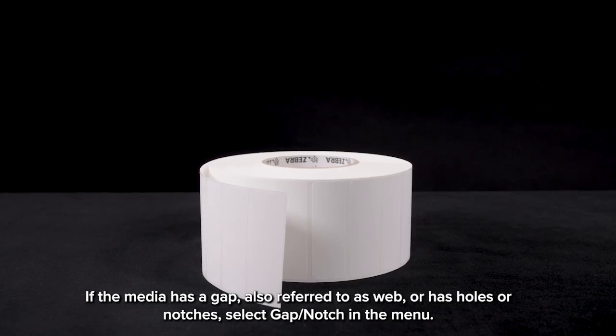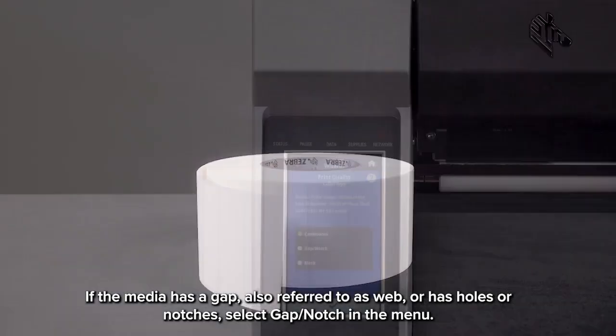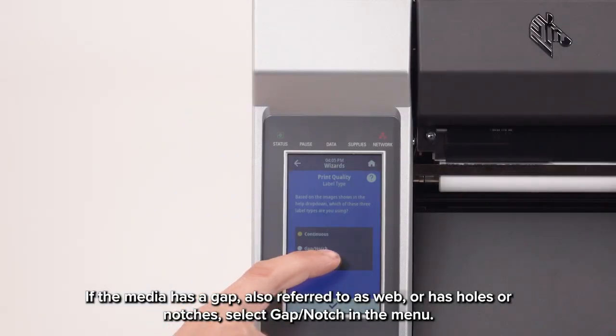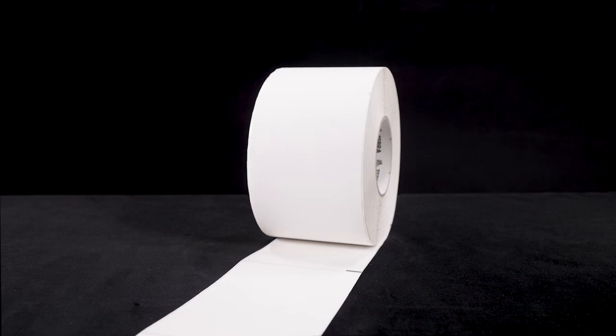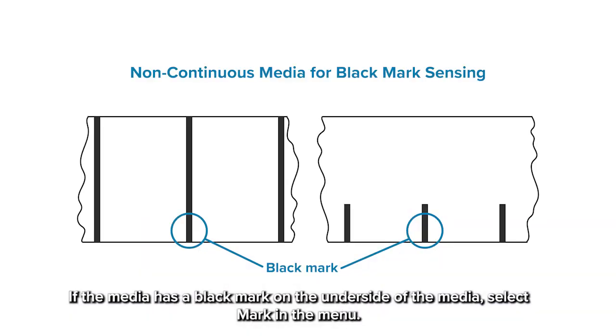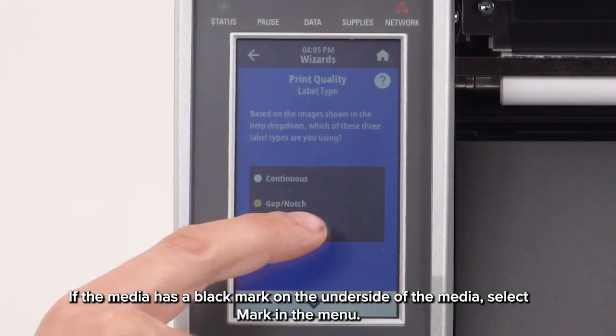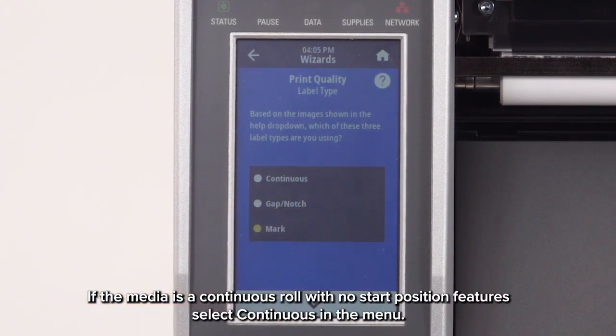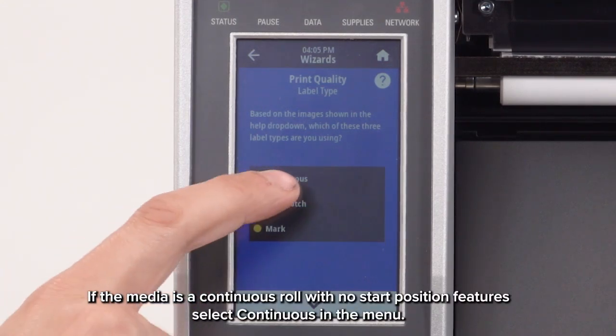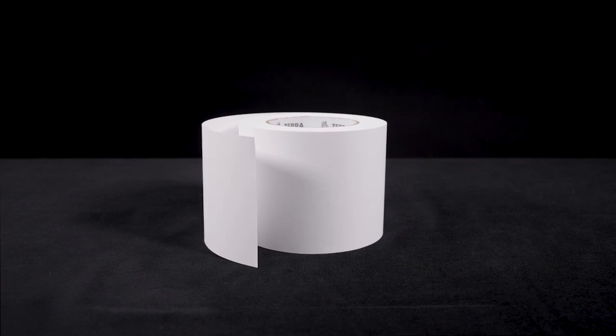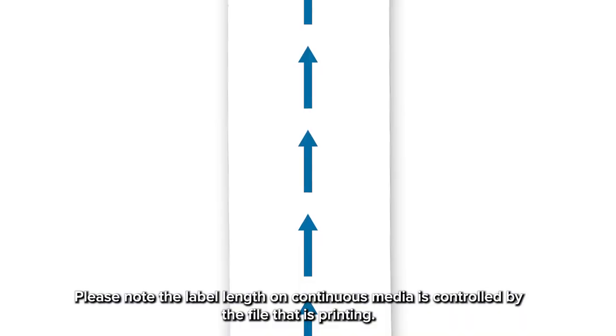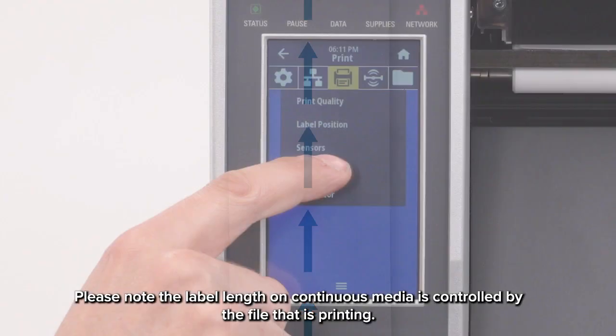If the media has a gap, also referred to as web, or has holes or notches, select gap/notch in the menu. If the media has a black mark on the underside, select mark in the menu. If the media is a continuous roll with no start position feature, select continuous in the menu. Note the label length on continuous media is controlled by the file that is printing.